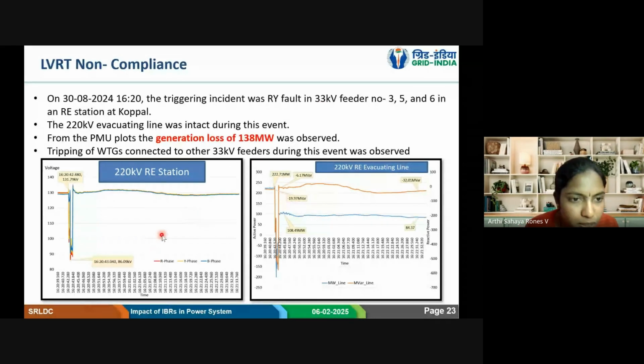Because the voltage is within the LVRT limit, still a few inverters have tripped. If we see this side, we have the RE station voltage, all three phase voltages. Initially there is a dip in R and Y phase, and subsequently a dip in R, Y, and B phase voltages. And if we see the P and Q of the plant, initially the plant was evacuating 227 megawatt. After the event, it has reduced to 108 megawatt.